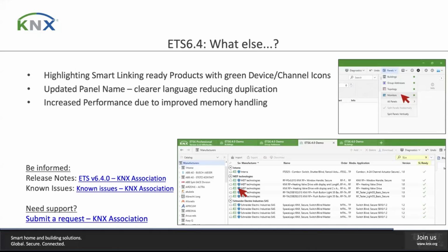So when this comes out in what's called a turtle export, which is a new type of export file that we've got in ETS 6, that's going to have all that semantic information in there as well, which means a visualization can make very quick and easy decisions about how to render a particular set of group addresses. It's going to know, well, this is a dim light, so I'm going to display a dim light function here rather than just some generic options, or have to have it set up by the integrator. So it's going to make for very rapid visualization.